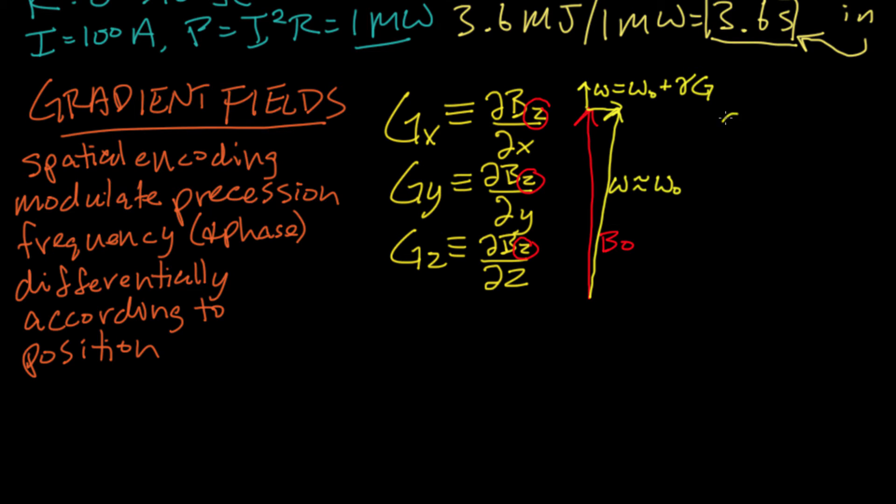The z direction, which is defined by the direction of the main field, is along the axis of the bore as shown before. For a z gradient coil, the symmetry of the gradient coil windings are as follows. They have the symmetry of two counter-rotating loops, and as you can imagine, the z component of the field that's generated by those loops will have a strong dependence on z.